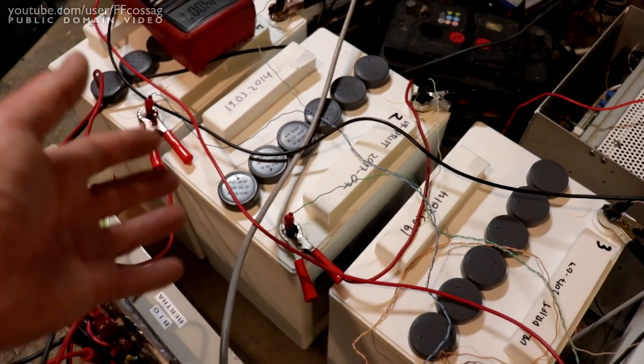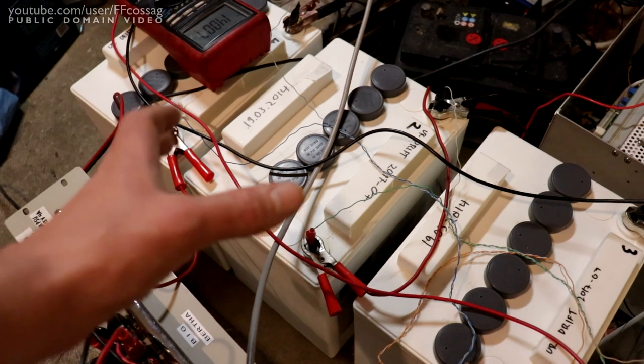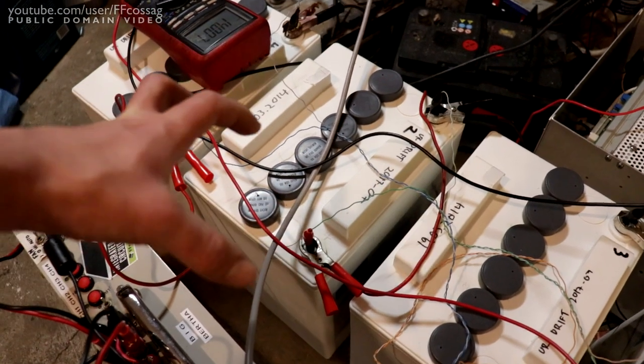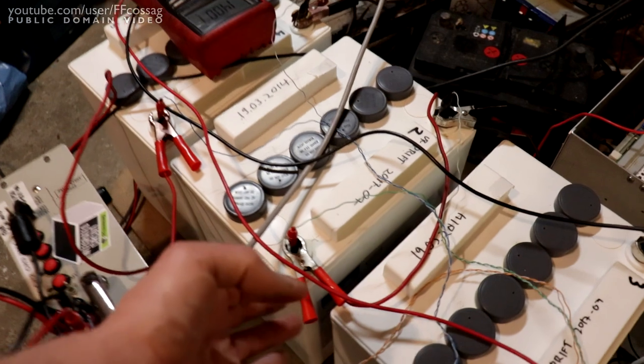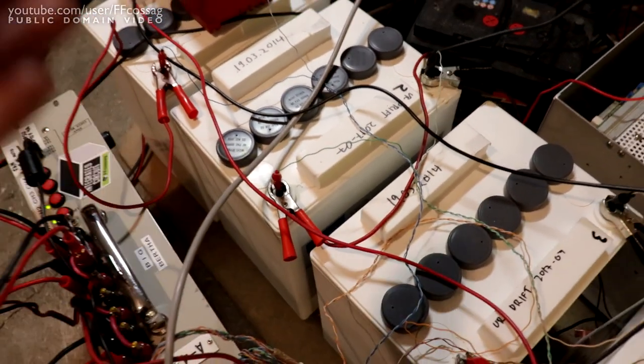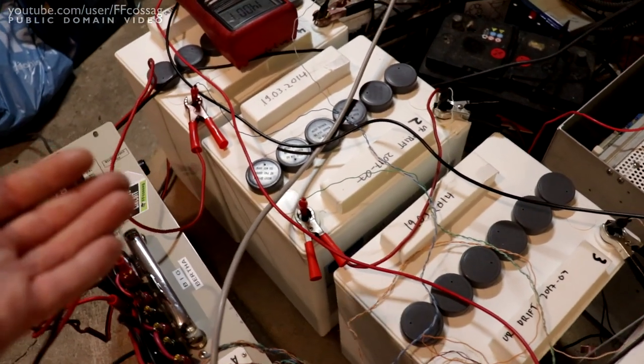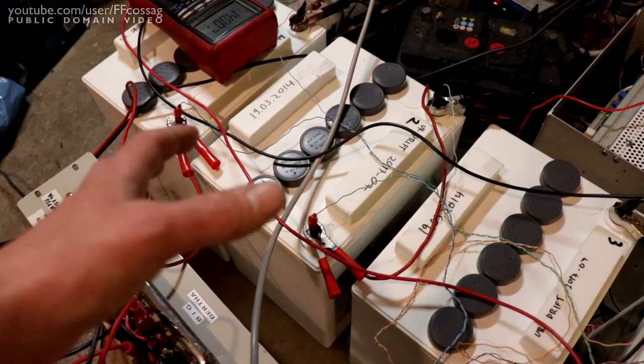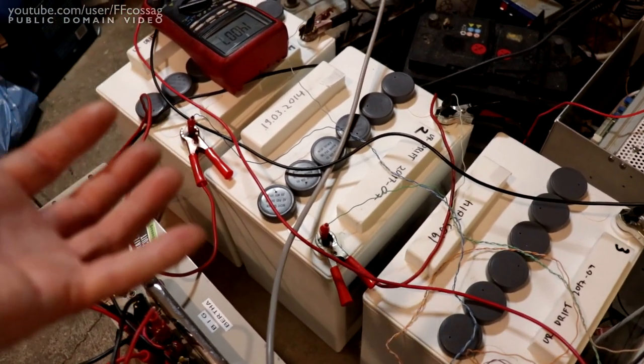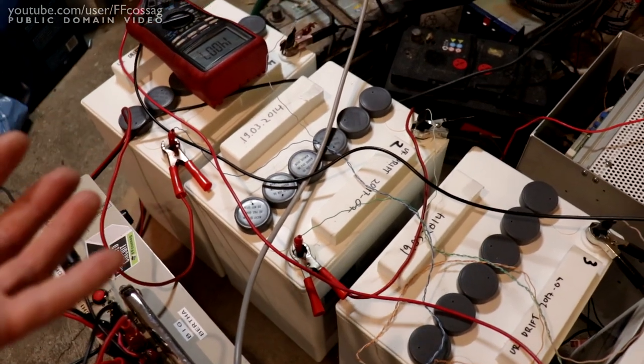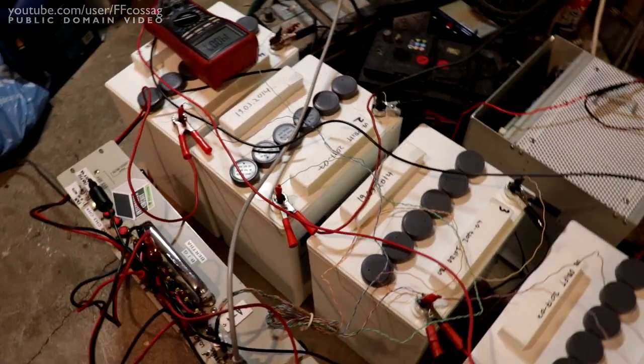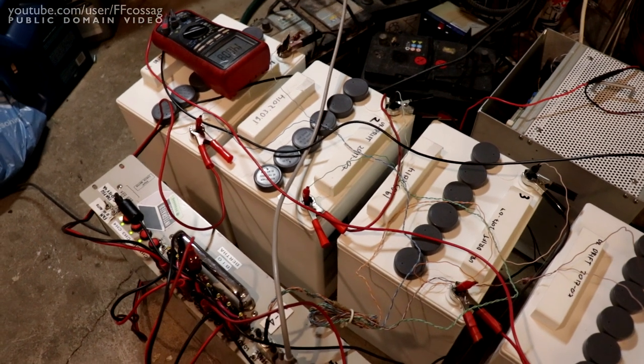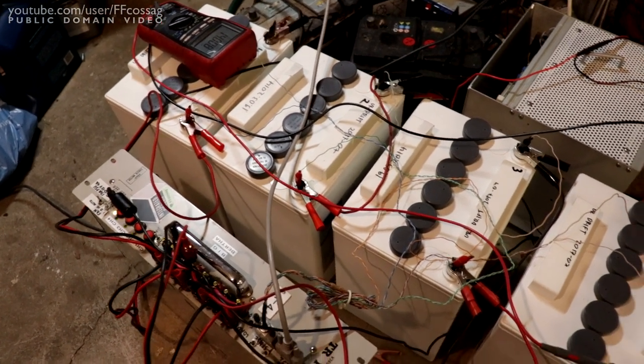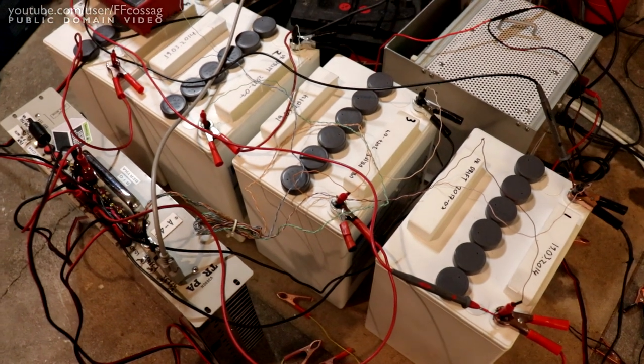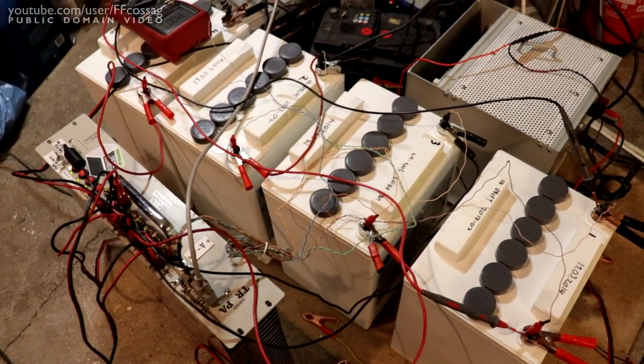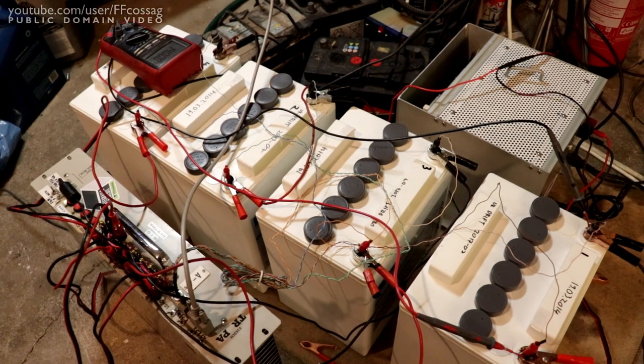And due to positive plate expansion, some of these are actually known to crack open the cases when they get old. They don't have the fancy Sonnenschein terminals that I have on my big fancy 2-volt cells, so there's really no place for the terminal to go when it starts expanding with age. This seems to be a bigger problem with cycles than with standby use, so we're going to see if these guys are just going to crack open if I put them in service and if they are in useful shape.